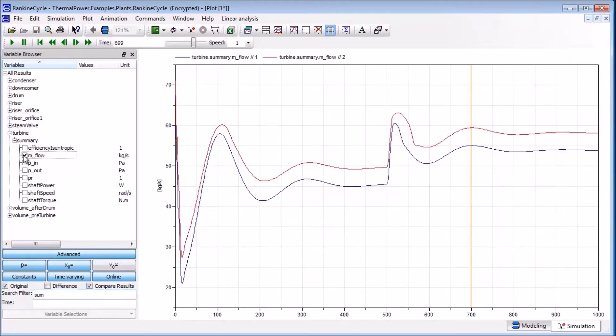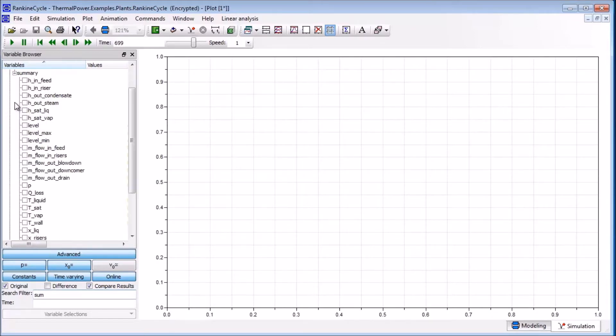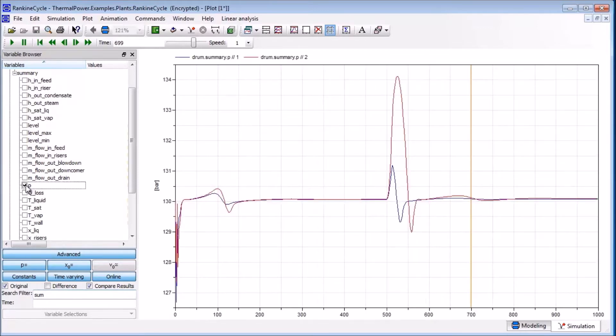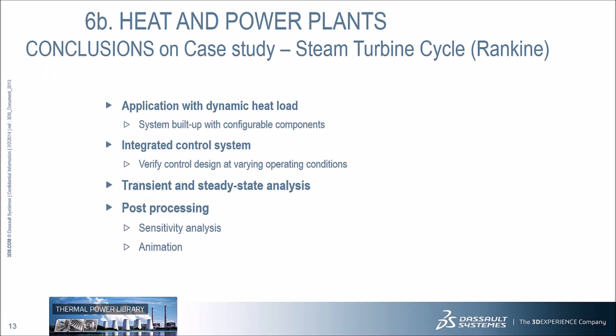We can also look at the drum pressure and see how the pressure controller handles the extra heat. As expected, the extra heat gives a higher peak in the pressure during the load change. We have demonstrated a dynamic model of a Rankine cycle with a heat load boundary condition applied with a ramp. The system was assembled from standard, parameterized, and fully configurable components, including a control system for drum pressure and level. This model can analyze both transient and steady-state behavior. We also demonstrated post-processing in Dymola, including basic plotting, animation of the diagram layer, sensitivity analysis by changing parameter settings, and the Compare Results feature.